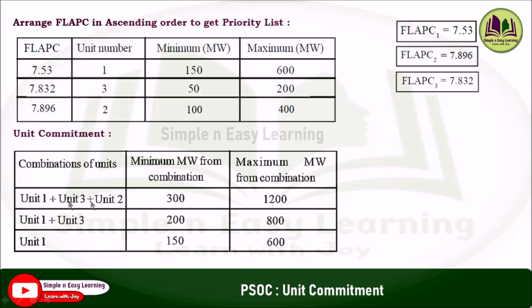The first combination includes all three units — unit 1, unit 3, and unit 2 — giving a minimum of 300 MW and a maximum of 1200 MW. The second combination leaves out the least-priority unit 2, keeping unit 1 and unit 3, with a minimum limit of 200 MW and a maximum limit of 800 MW (600 + 200).